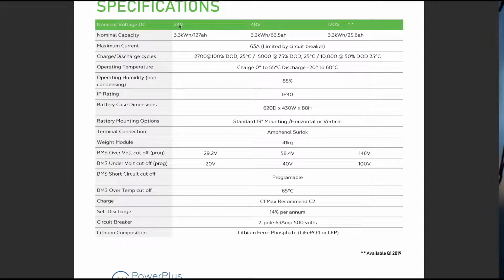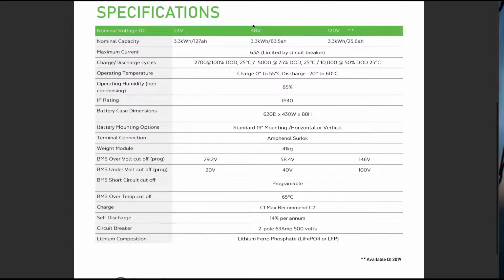And you'll see they have a 24, 48 and 120 volt model. So we'll look at the 48 volt model here, and we'll do a comparison with, we're choosing to use lithium ion as opposed to a lead acid sealed cell, and try and build something of similar capacity. We'll go down here, so it's 3.3 kilowatt hours per battery module.